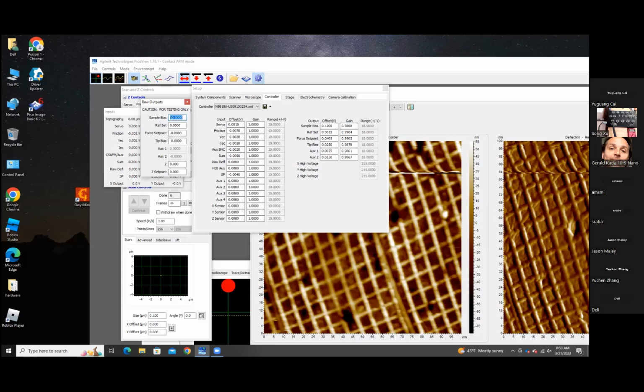So really all we're doing is making sure that you can get to those limits, but you're not going to be dead on 10 volts. It'll probably be slightly higher. Yes, it's actually 10 volts, but the last digit flicks a little bit up and down. And then check your negative 10 as well. It's negative 10. Good, 9.99. And then, just for safety reasons, go back to 0, so that we don't shock ourselves.